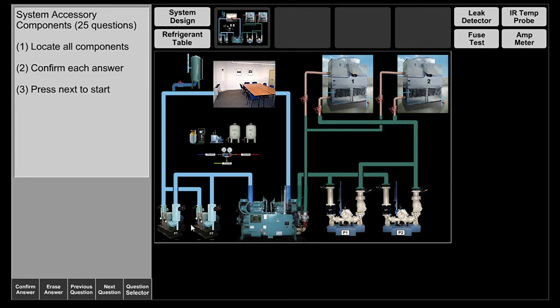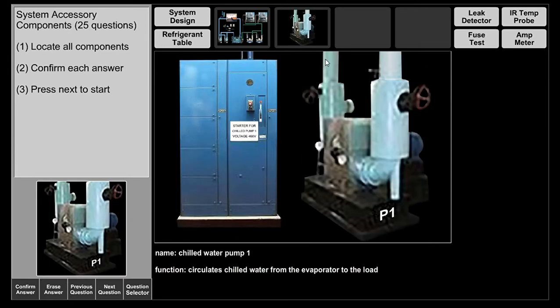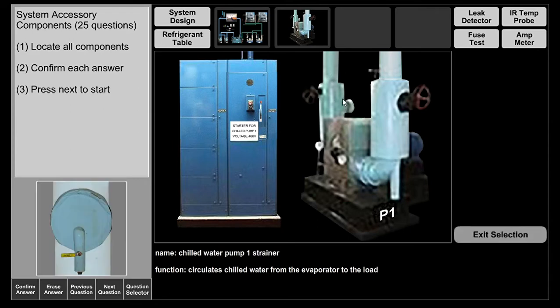As it comes through, it enters what we call the pump suction — this applies to both pumps. Water comes back through an isolation valve, which is fully open during operation. It then meets a strainer, which picks up any slag from the pipe and any impurities inside the piping — sometimes called tower fill and pipe slag — preventing them from circulating through the system and possibly damaging the pump.